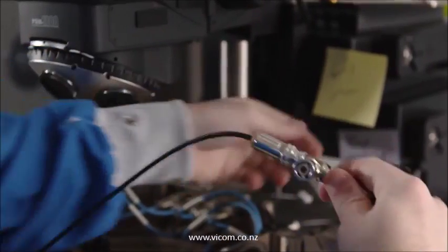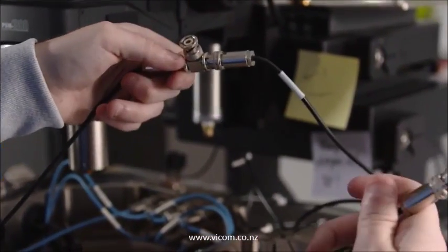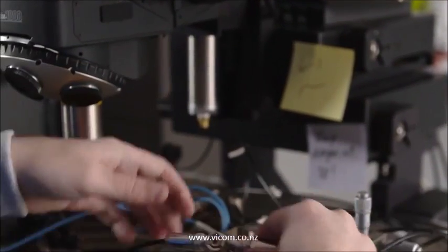We're here today in the Keithley Labs to show you a few tips and techniques on how you can make AC impedance measurements along with DC IV measurements. As some of you may have experienced, when making these different types of measurements, you have to end up changing your test setup, change your cables, even lift the probe needles off your device under test in order to make the change in the setup. This often is very time consuming and can lead to errors. So let us show you how to make these measurements much easier and give you confidence that the results you're getting are accurate. Let me show you how easy it is to make IV and CV measurements automatically.